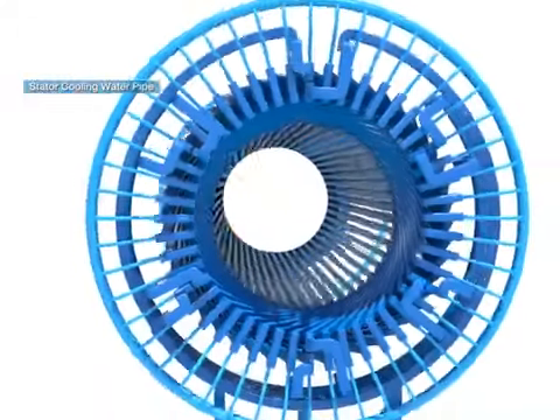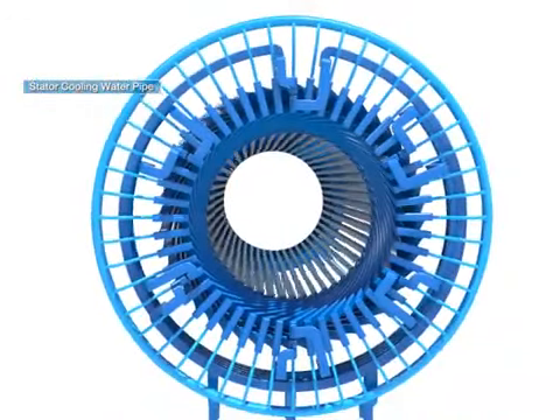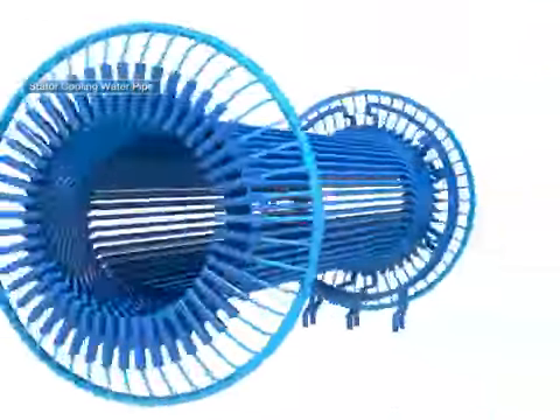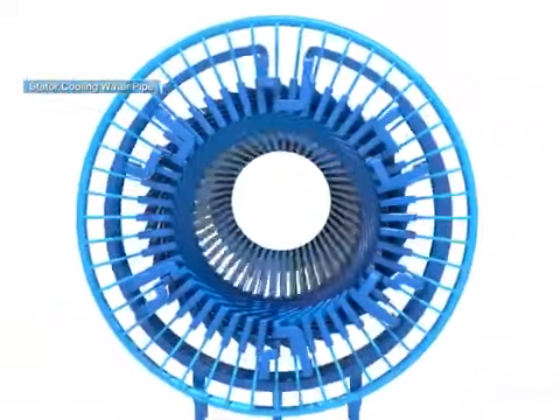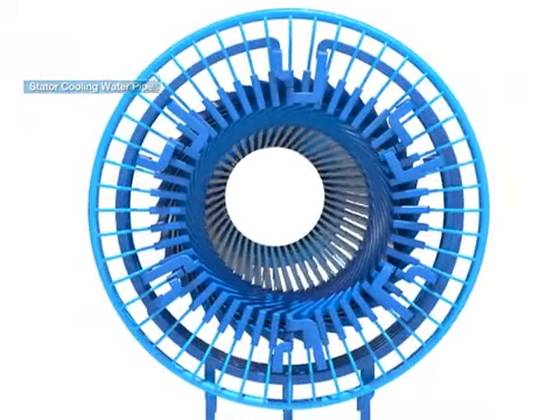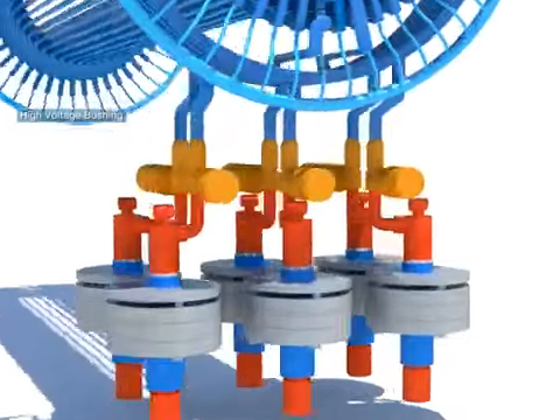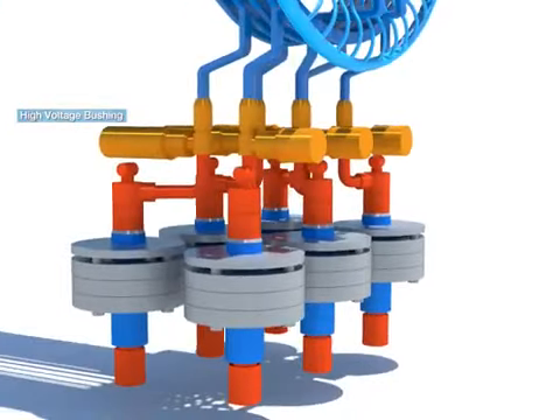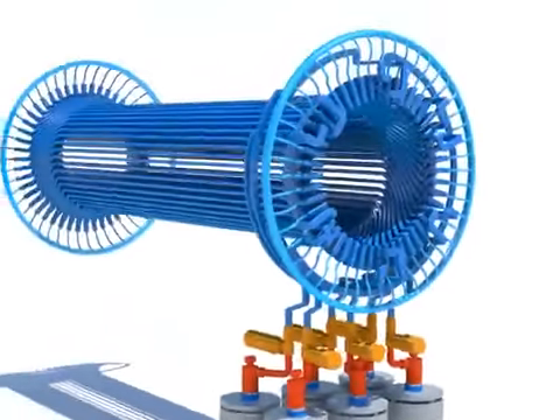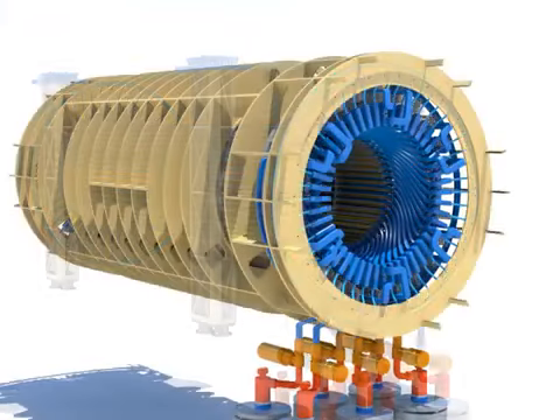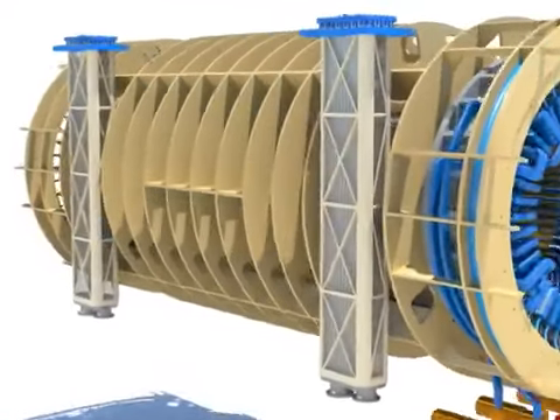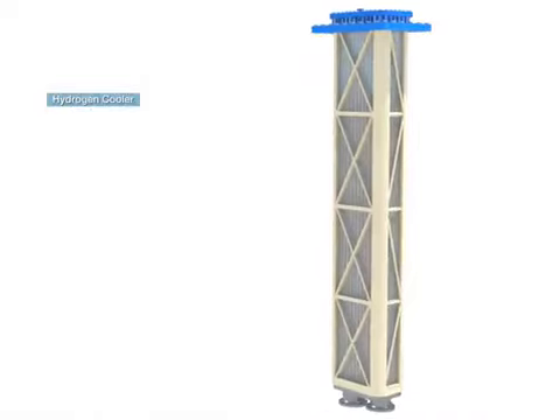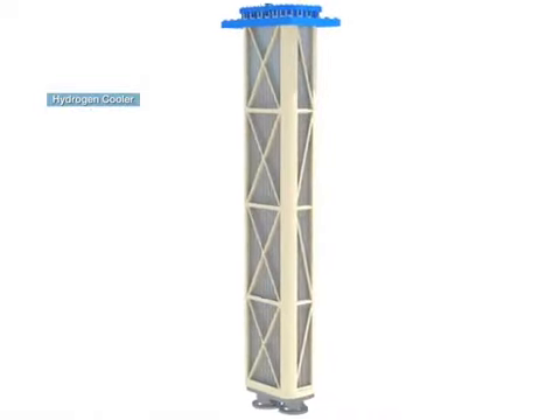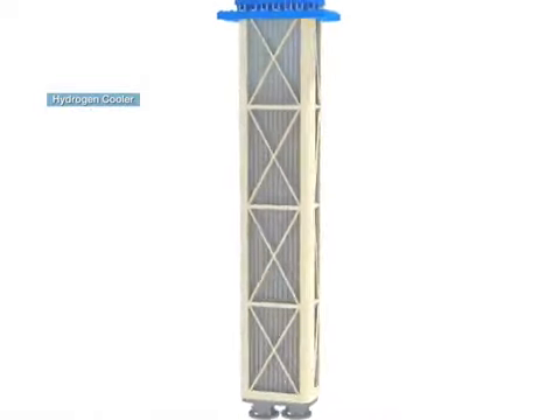The stator cooling water pipe is a device for providing cooling water to the generator stator winding. The high voltage bushing refers to the withdrawal terminals of the stator winding. The hydrogen cooler is a heat exchanger for cooling hydrogen, which is used as cooling gas for the generator rotor.